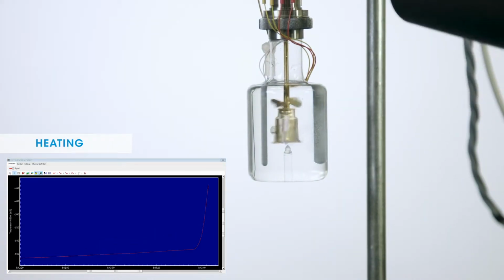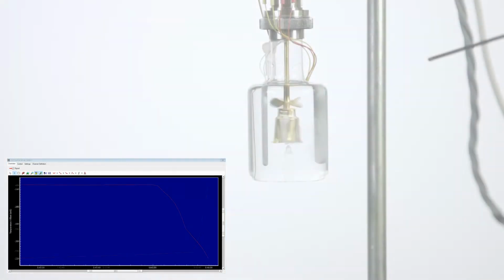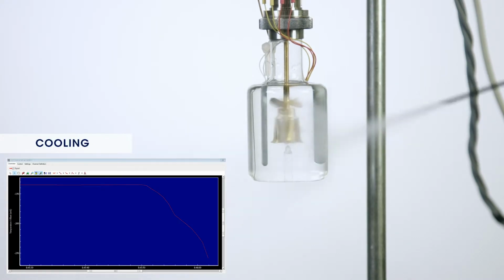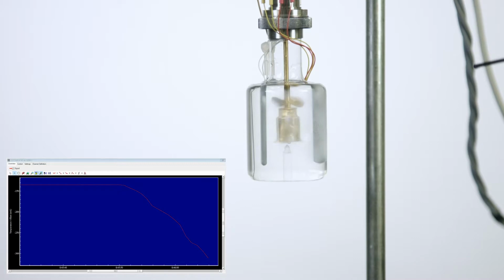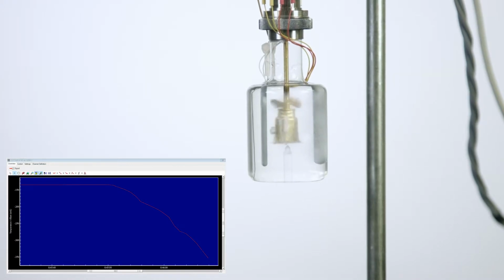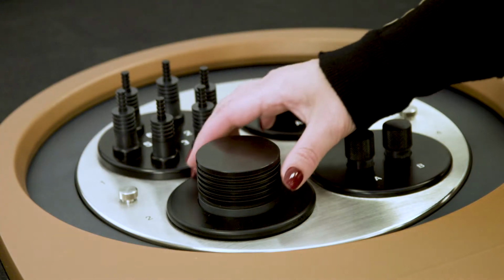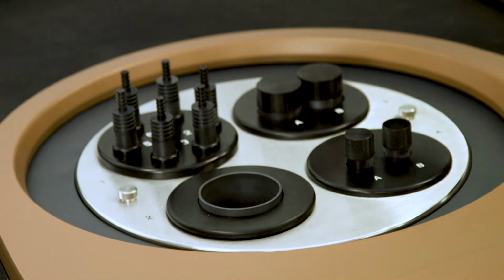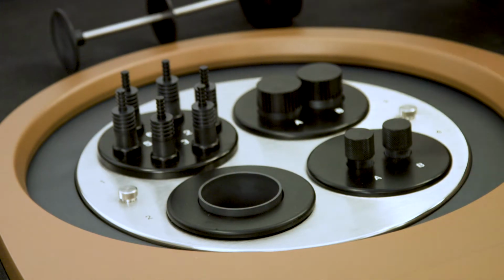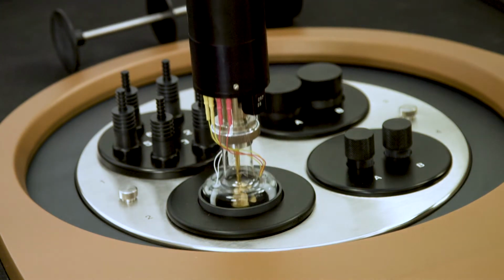Heating can be done with your hands or a hairdryer. Cooling can be done with acetone or a cooling spray. Make sure to move the spray over the surface to avoid cracking of the glass. When the temperature is in a suitable range, lower the SolCal into the thermostat.